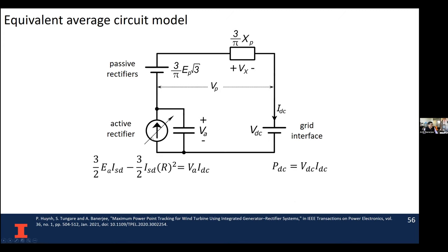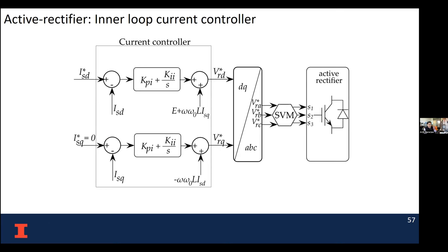And with the active rectifier, you can control the current. Think about it this way: there are two things going on. If you maintain the DC bus voltage, and the passive rectifier voltage is governed by the generator speed, that voltage is determined based on KVL. If I can control the current, this voltage is maintained constant, and whatever current I feed into this port has to go to the DC bus. That's exactly what we did—even though we don't have full control on the machine, by controlling the active port we can achieve power flow control. This is a standard inner loop control, nothing novel here, but we control the active rectifier using DQ current controllers.